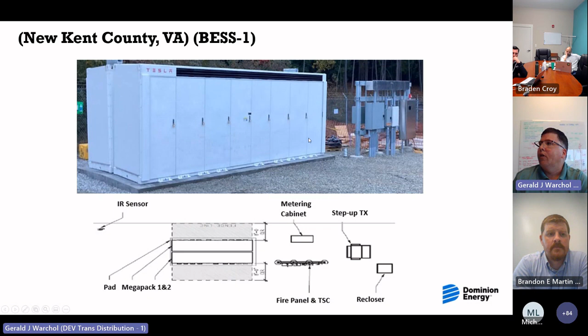This fire panel here and the IR camera are very important for lithium-ion batteries. In the worst case scenario, I think people have seen the press on thermal runaway. The fire panel is the computer system that looks at thermal conditions to safely shut down the energy storage system. And then we actually designed in the IR camera as a redundant engineering safeguard, to make sure that if the controls of this new system, which we didn't have any experience with, did not work, we had a secondary measure to turn the system off.